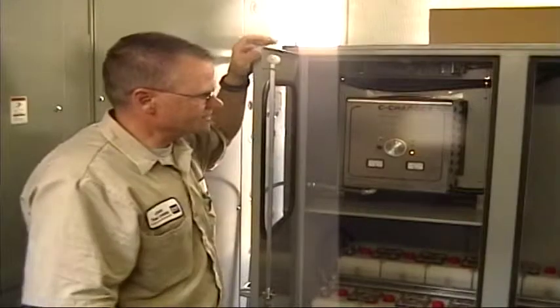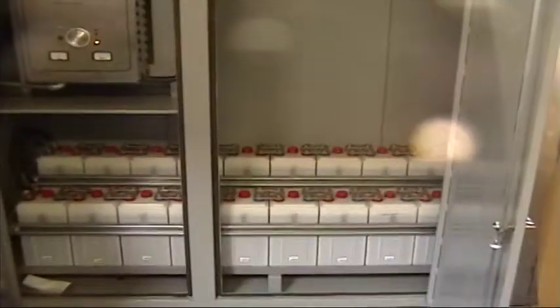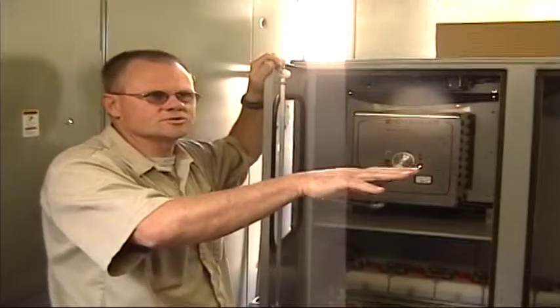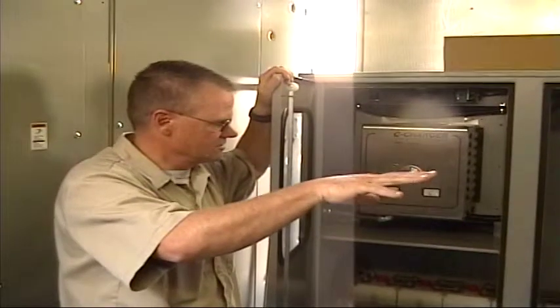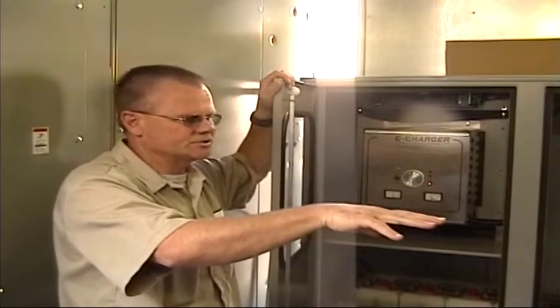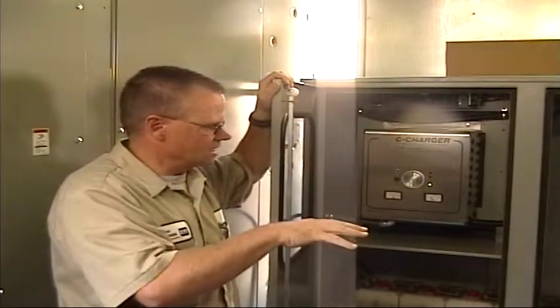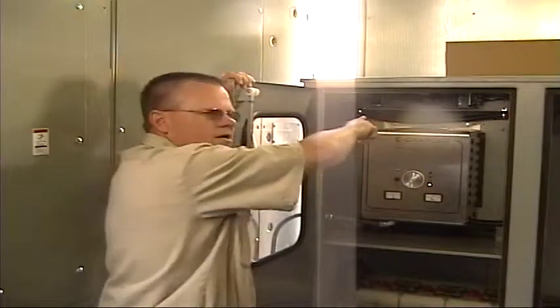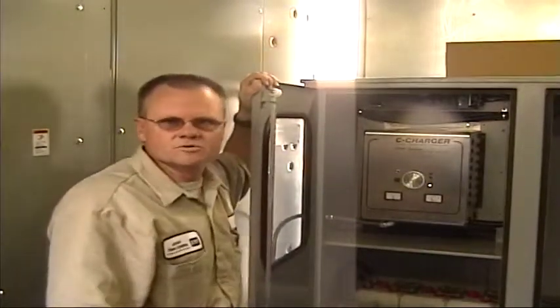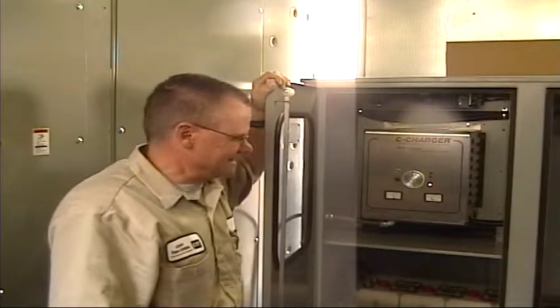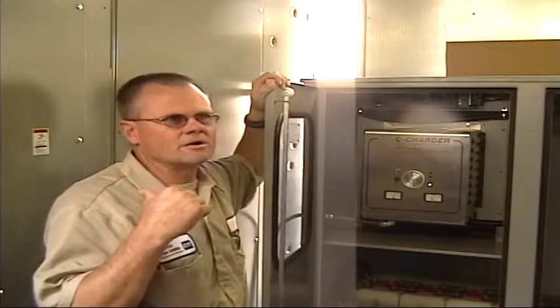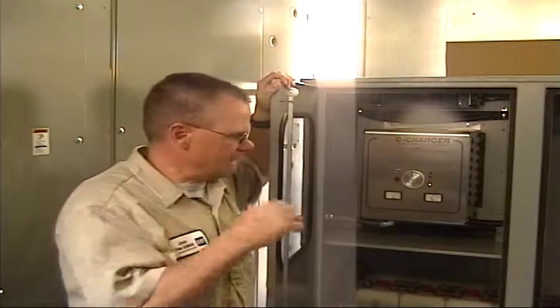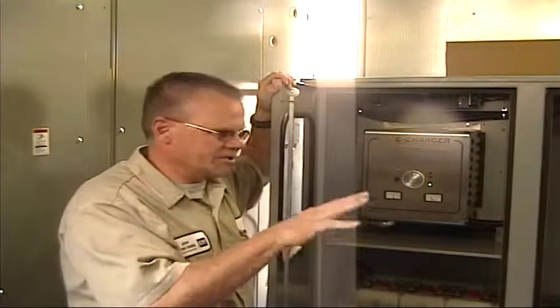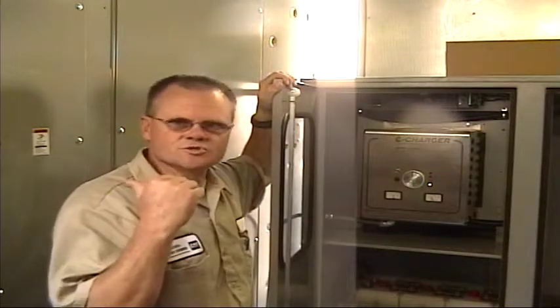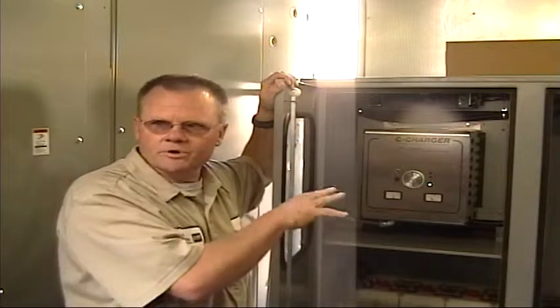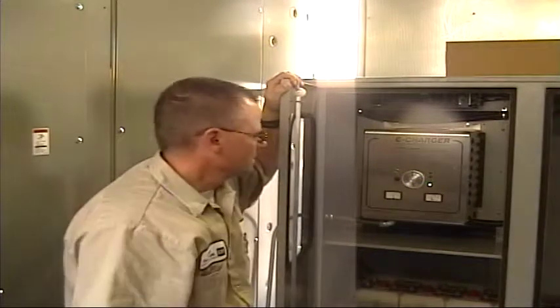This is an ICAD battery set that supplies the battery voltage for the DC controls, the 24 volt DC control for the engine generator package, and also through a converter up here converts 24 volts to 48 volts DC for switchgear control power. So the battery pack serves a double duty, not only to start the unit but it also controls the switchgear, so it's a pretty important component in this whole setup.